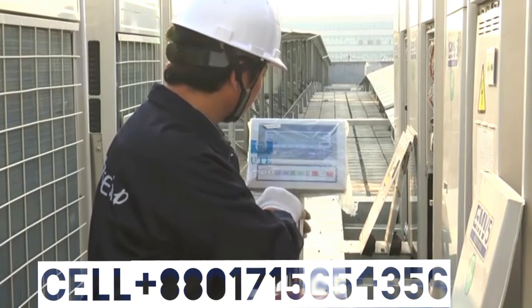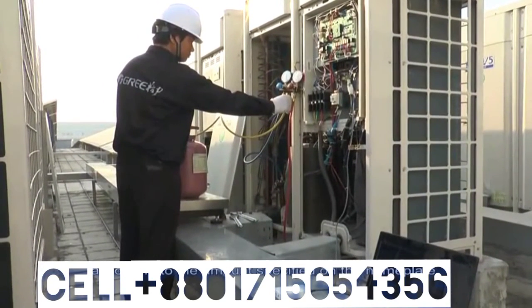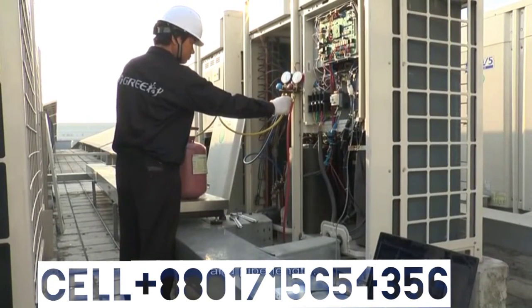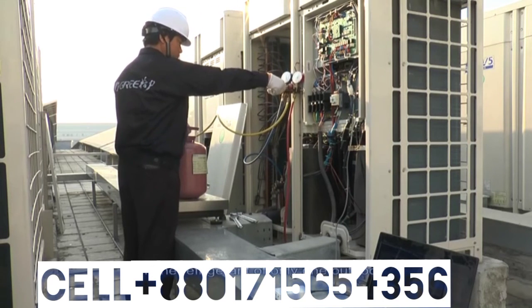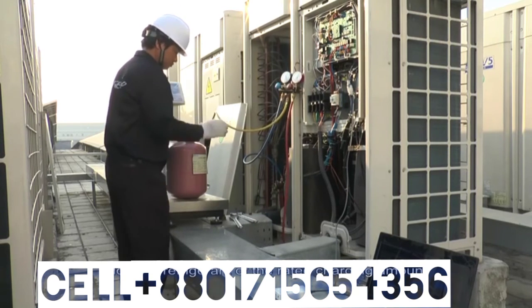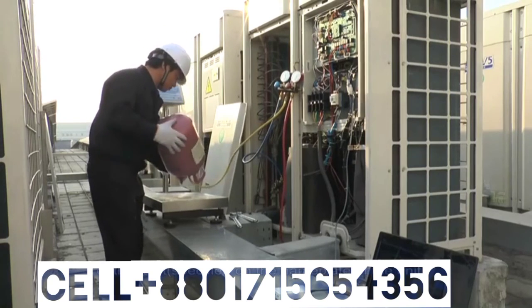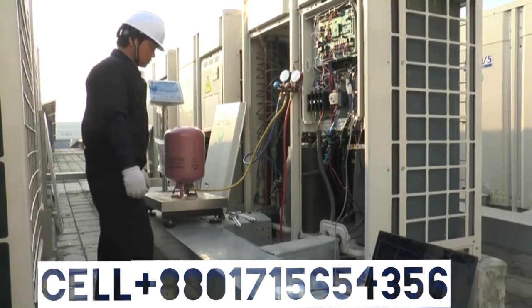If the refrigerant is proved satisfactory, calculate the additional refrigerant charging amount according to the amount specified on the nameplate and pipe length. For a multi-modular system installation, if the refrigerant of only one outdoor is drawn out before maintenance, add 80% refrigerant of the rated charging amount of that unit, specified on the nameplate of the unit. Start the system for a debugging test.